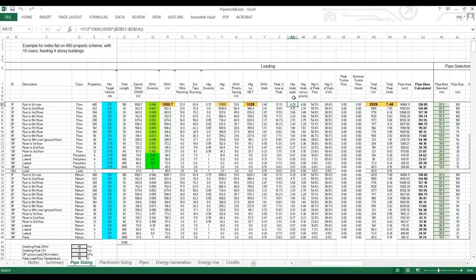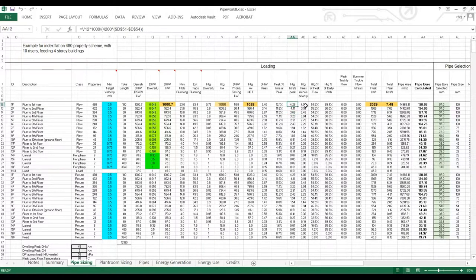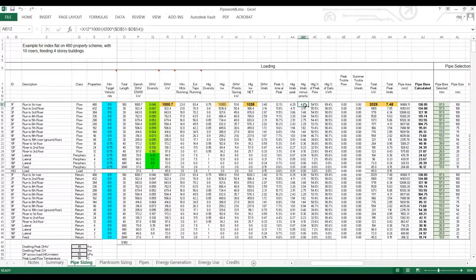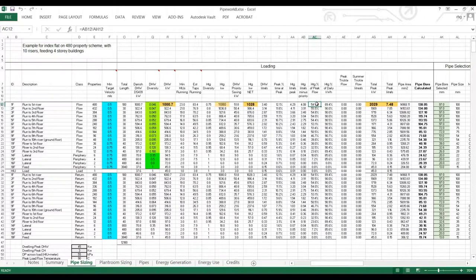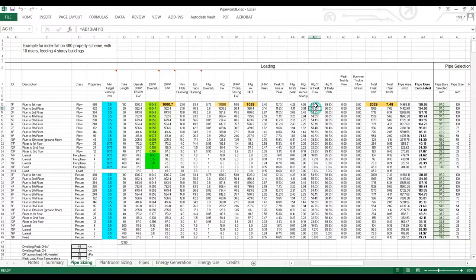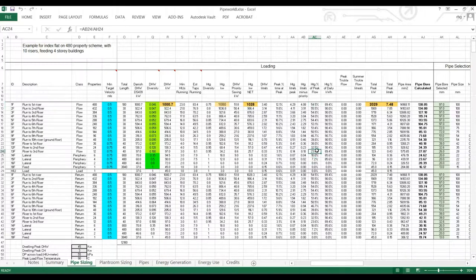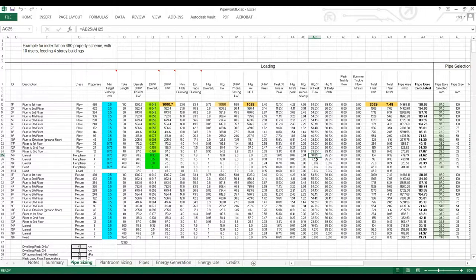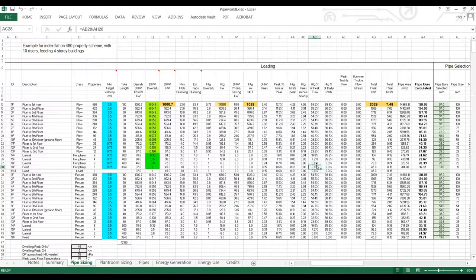We have the heating litres per second at peak. So this is the velocity running heating at peak load, and then taking away from that the priority if we have hot water priority on. So there's a few HIUs running hot water. We have a column here, the heating is a percentage of peak flow. So it's showing us here, coming out of the plant room, heating accounts for just over half of the peak load. As we get near properties, it's the instantaneous load that takes over. When we get right to the last property, the heating percentage peak is zero because we'll be running hot water. And with hot water priority, there will be no heating load.